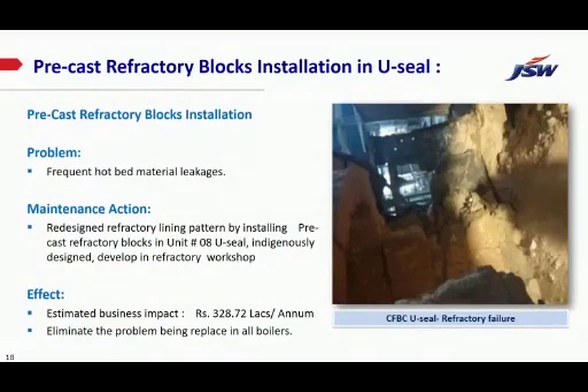In these images, these precast can be used widely. Initially, it was designed for the target areas, but now with some modification, it can also be used for the cyclone area, for the U-seal area, and crossover ducts, and inside cyclone inlets and inside walls too. The U-seal is a very complex shape, and it is very hard to provide conventional casting in such complex areas. So that's why the precast was designed for the U-seal.